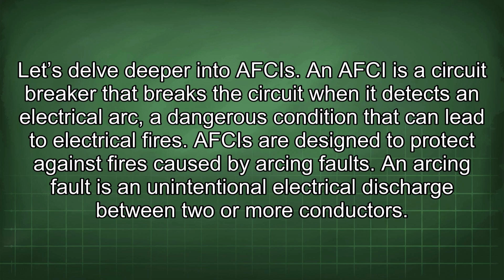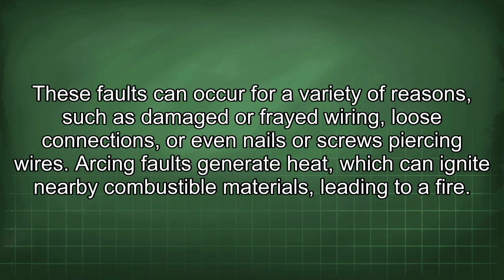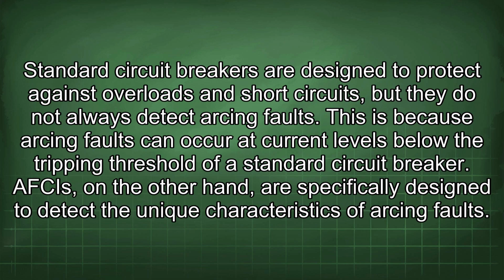An arcing fault is an unintentional electrical discharge between 2 or more conductors. These faults can occur for a variety of reasons, such as damaged or frayed wiring, loose connections, or even nails or screws piercing wires. Arcing faults generate heat, which can ignite nearby combustible materials, leading to a fire. Standard circuit breakers are designed to protect against overloads and short circuits, but they do not always detect arcing faults. This is because arcing faults can occur at current levels below the tripping threshold of a standard circuit breaker.